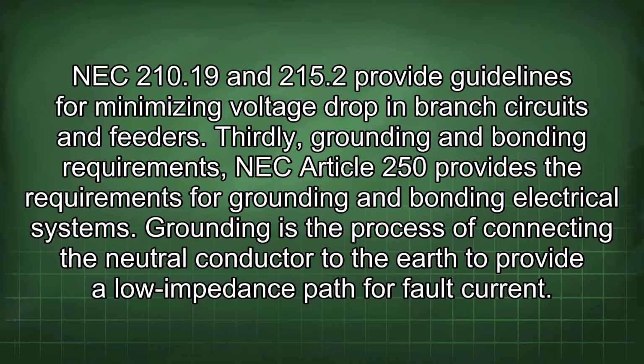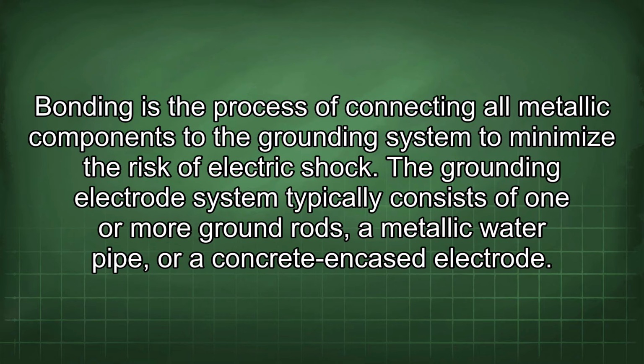Thirdly, grounding and bonding requirements. NEC Article 250 provides the requirements for grounding and bonding electrical systems. Grounding is the process of connecting the neutral conductor to the earth to provide a low impedance path for fault current. Bonding is the process of connecting all metallic components to the grounding system to minimize the risk of electric shock.